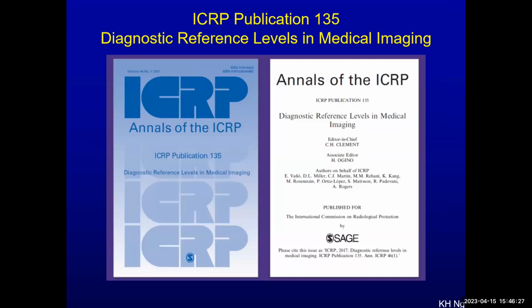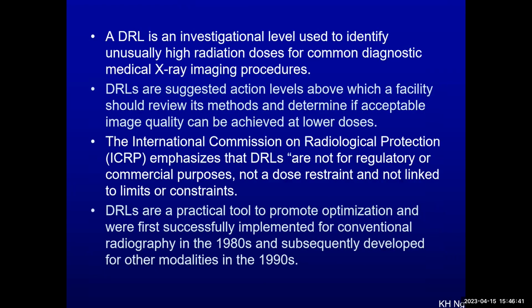The last part is the DRL, a bit about that. The ICRP published Publication 135 on DRLs in medical imaging. That serves as a standard reference, and then the IAEA started activities on that. It is an investigative tool to identify higher or lower dose. So it suggests an action level you can take to review our methods and how we can improve. It's not for regulatory or commercial purposes.